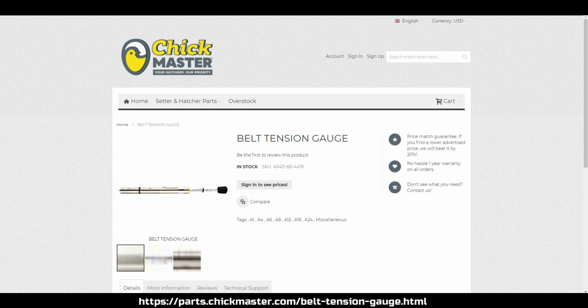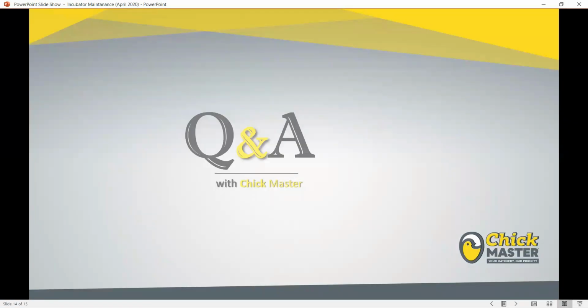Is there a standard amount of deflection you should be looking for when you're tensioning? The amount of deflection is always going to be about 2 inches. What differs between machines and belts is the amount of force required to get to that 2 inches. Especially on new belts, in a machine where you've put a brand new belt in, you're going to find the amount of force is far greater. As the machine beds that belt in, as it gets up to temperature and gets used, the belt will become a little bit slacker. So it's entirely normal that once you put a new belt on the machine, you have to readdress that and maybe lift the motor plate slightly just to retighten it, maybe a week or two after it's been installed.